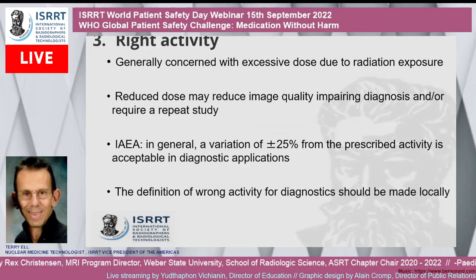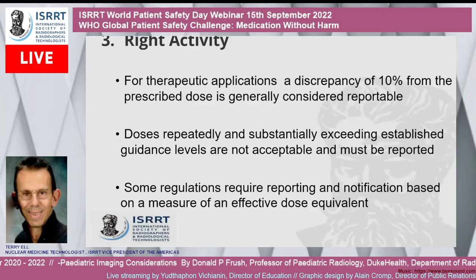For diagnostic radiopharmaceuticals, a variation of plus or minus 25% from the prescribed activity is generally considered acceptable, but you obviously need to follow local guidelines. A discrepancy of 10% from the prescribed dose in therapeutic applications is generally considered reportable. Recognize that even when individual doses are within an acceptable range, multiple repeated dosing also has potential of delivering a substantial effective dose equivalent.